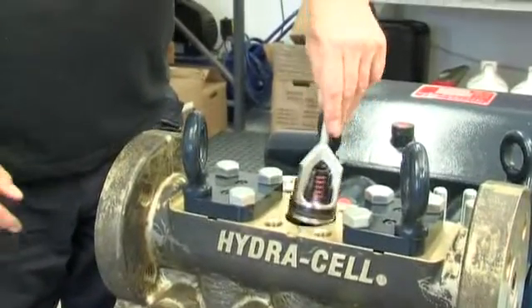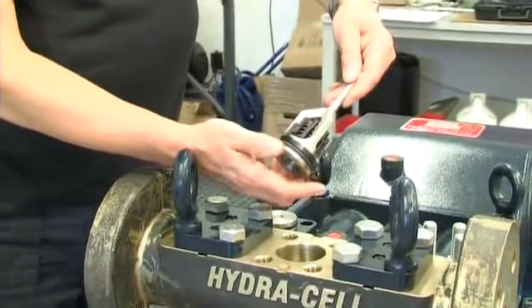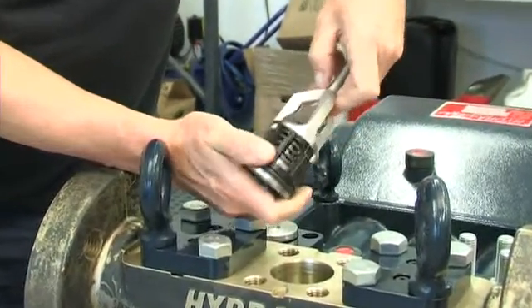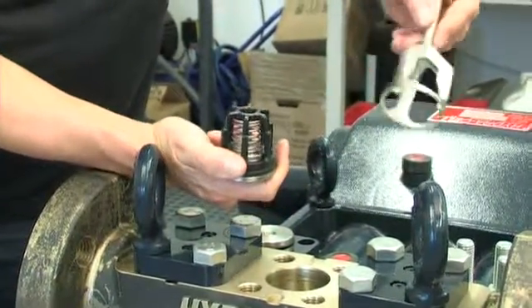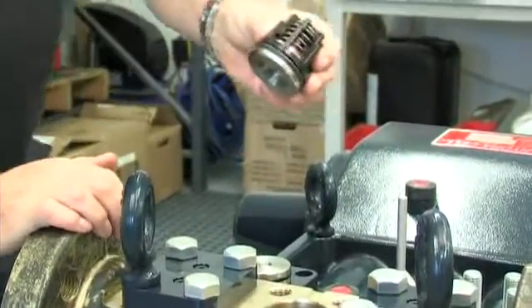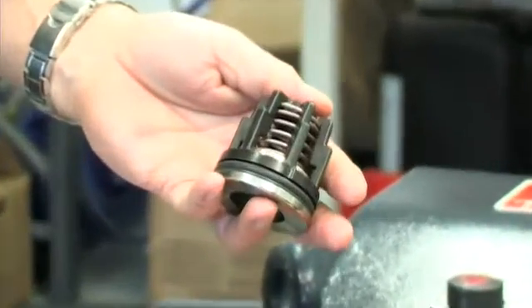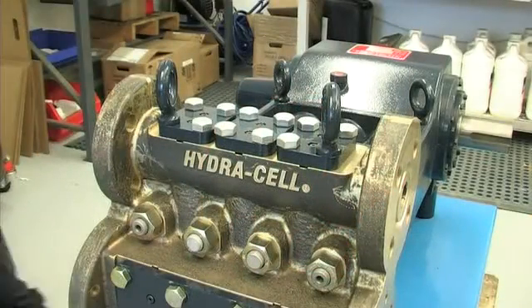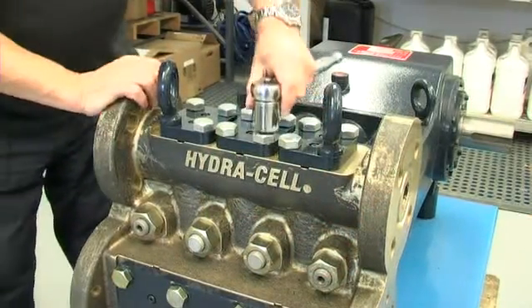Replacing the Outlet Valve Assembly. All valves in Hydra-Cell T-Series pumps are cartridge-type spring-loaded check valves, and replacing them is a relatively simple on-site procedure that can be carried out without removing the pump's liquid head or the associated pipework. Here we disassemble and reassemble the middle outlet valve, but the others are replaced in the same way.